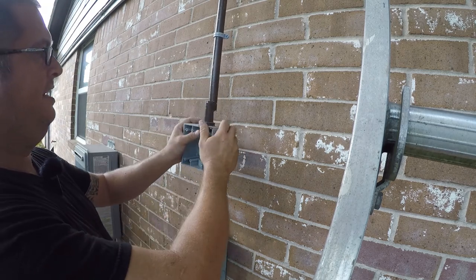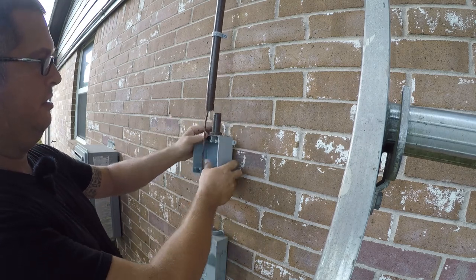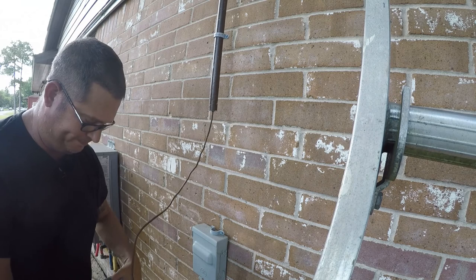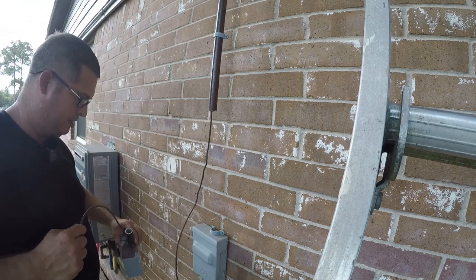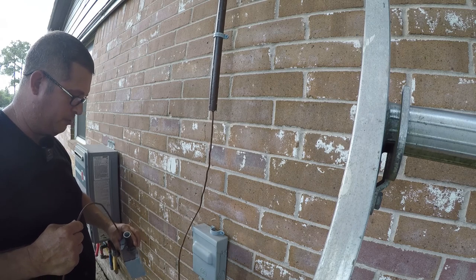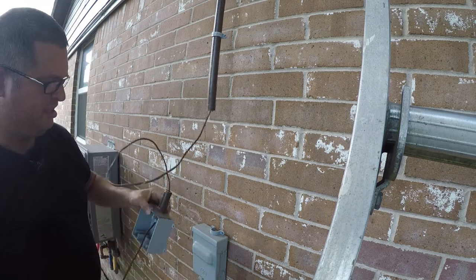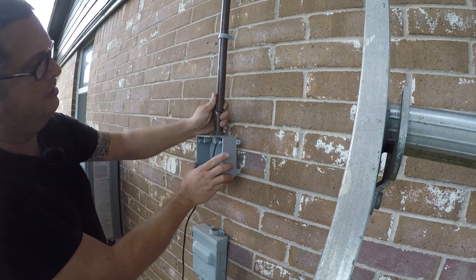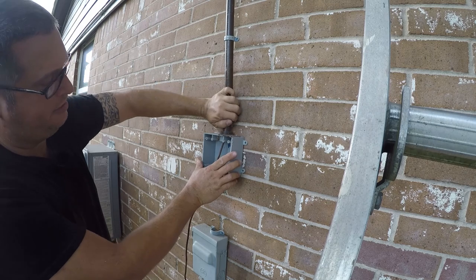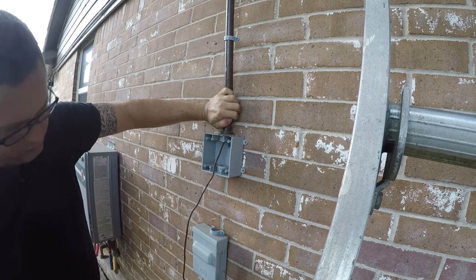So I think this could work. The reason this wire is going away is it's the wrong size. It calls for shielded wire for the control circuit. So let's see, what does that look like? Can we come off of here and be clear of that? Yeah, that'll work.